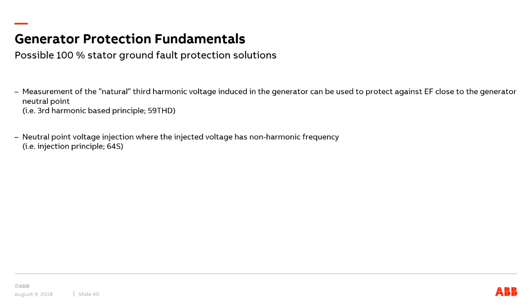If the third harmonic voltage is very small, another principle for 100% stator ground fault protection can be used, which is a non-harmonic voltage injection in the neutral point of the generator. If this injected voltage gives a corresponding current, this is an indication of a stator ground fault.